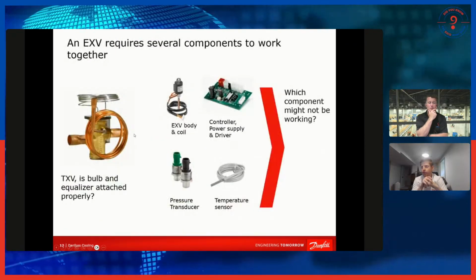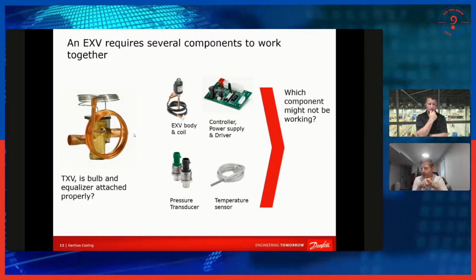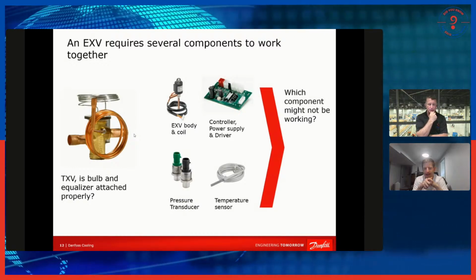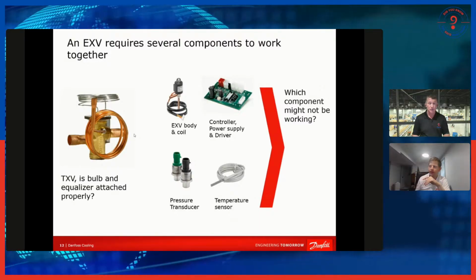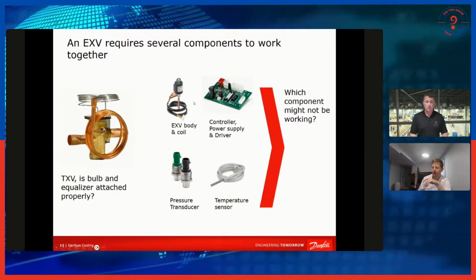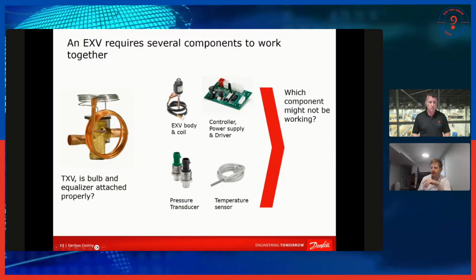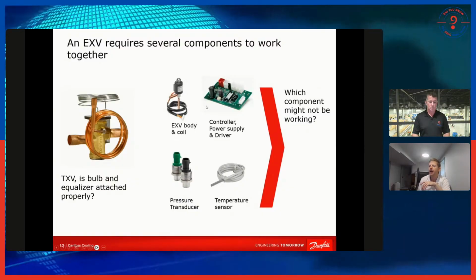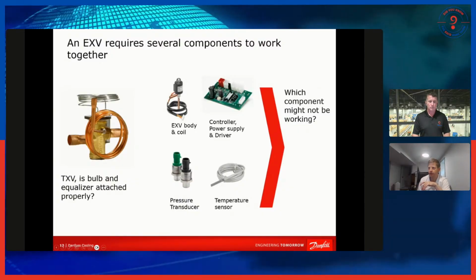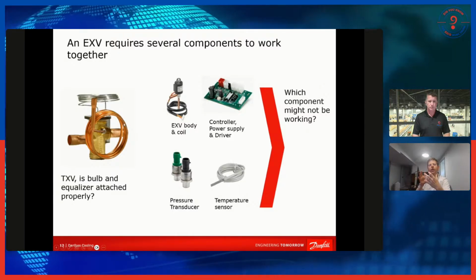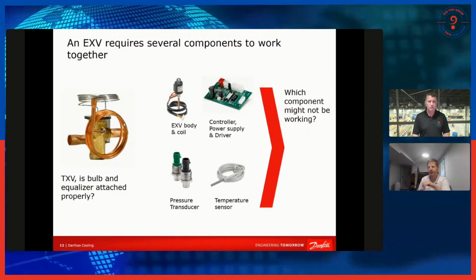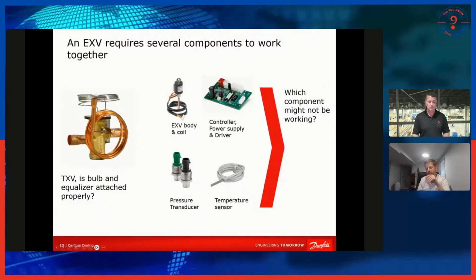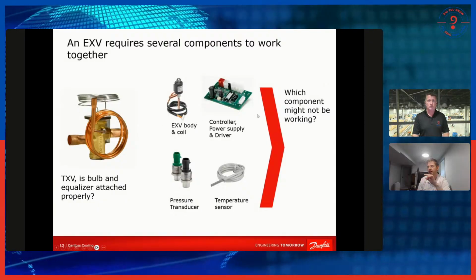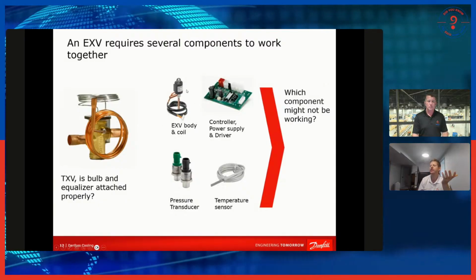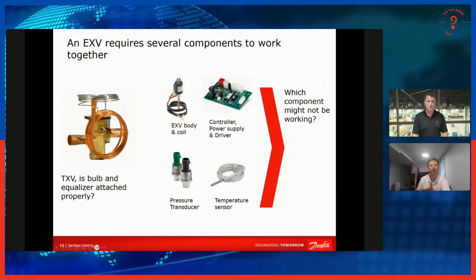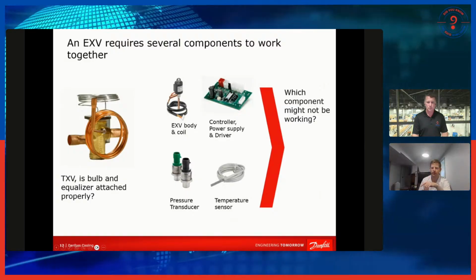So when troubleshooting an EXV, I like to try and isolate which component in this whole network of things that have to all work together is not potentially working right. With a TXV, you've got the bulb and the equalizer. It's kind of all part of one thing. It's one item, even though it's got different parts of it that kind of branch off and do their own things. But with an EXV, it's really important to figure out, okay, do I have a valve problem? Is my controller not working? Is my transducer not reading anymore?